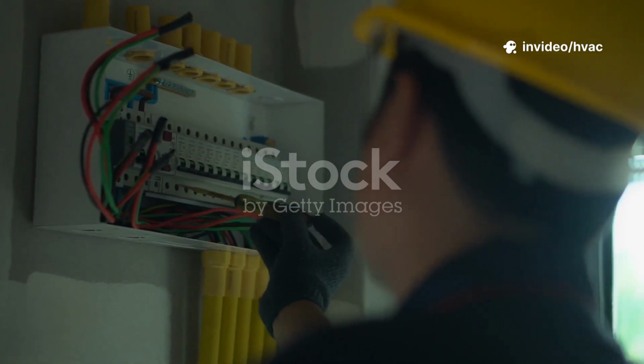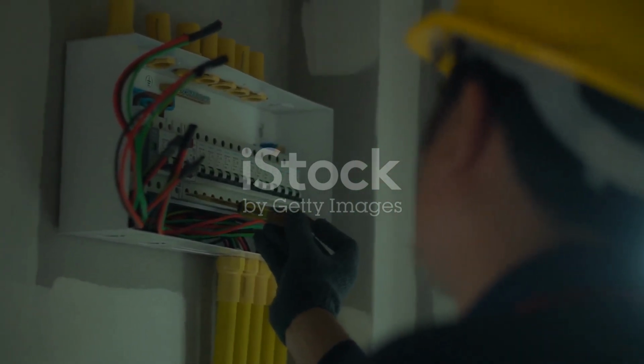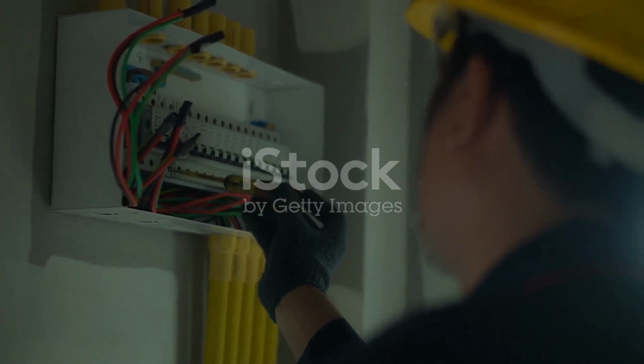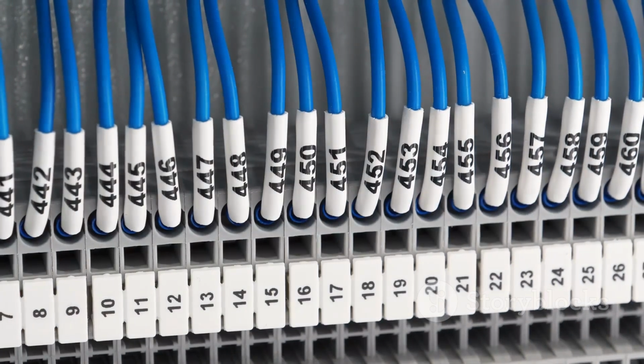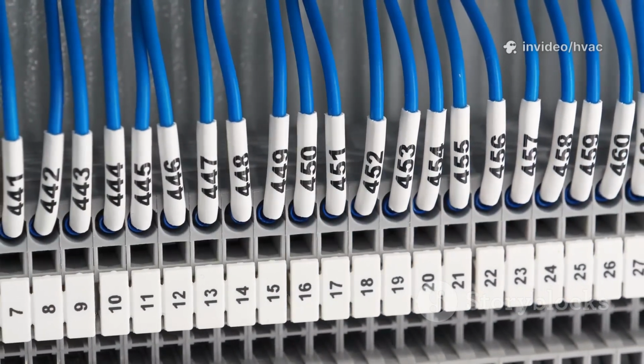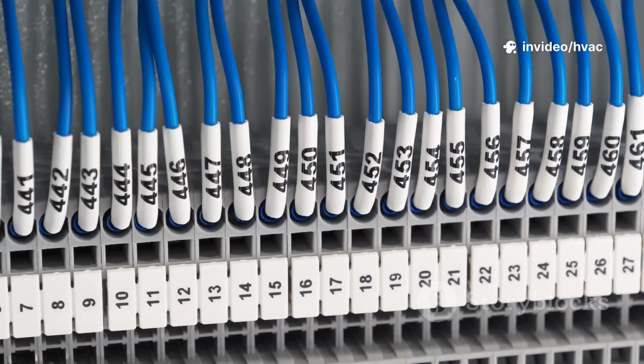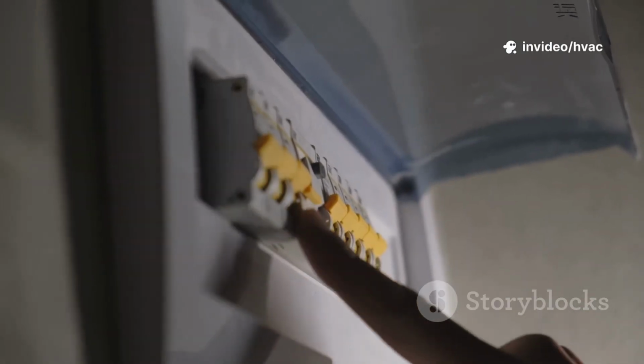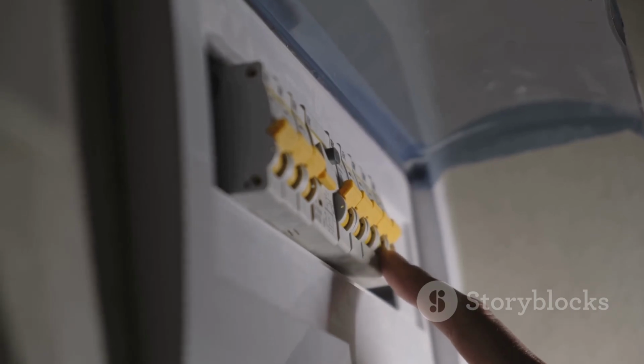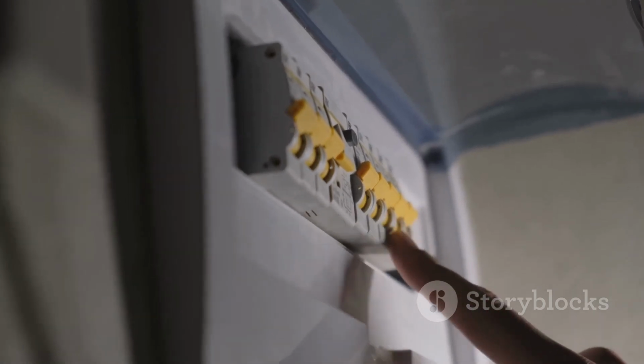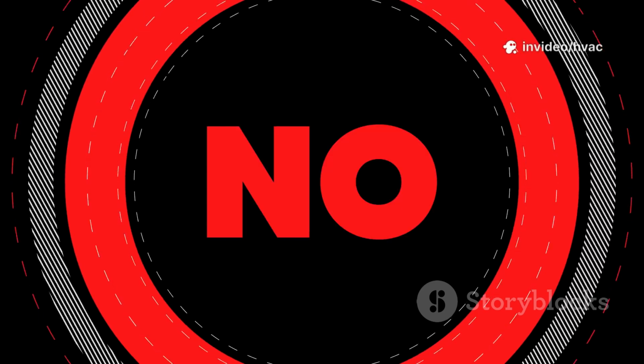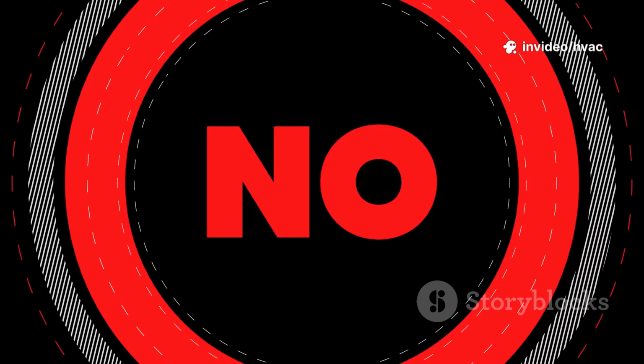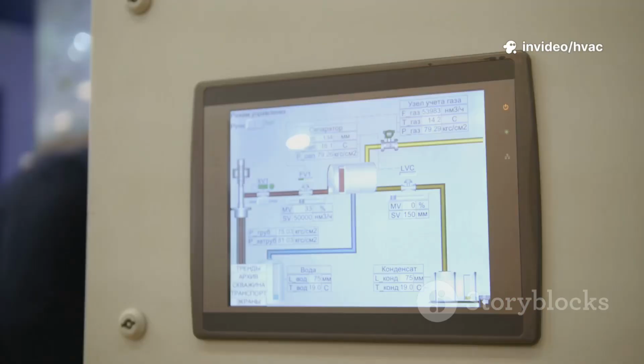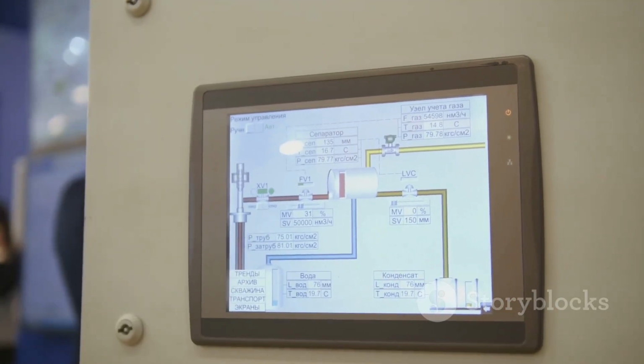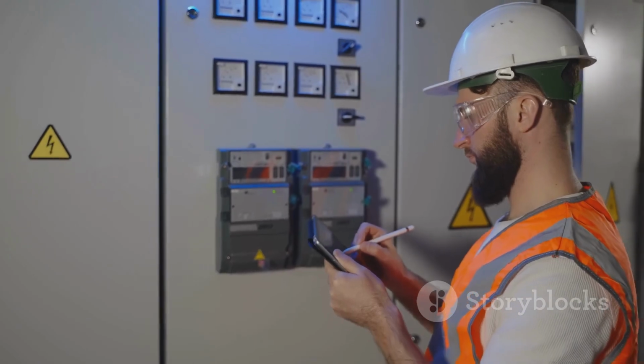At the heart of every interlock is a simple but crucial choice. Do you use a normally open, NO, or normally closed, NC contact? This decision shapes how your safety logic works, and it's vital for both safety and reliability. Here's the basic idea. A normally open, NO contact is like a door that stays open until you close it. No current flows until the device is activated. A normally closed, NC contact is like a door that stays shut. Current flows until you open it by activating the device. So how do you choose? Let's break it down step by step, using practical HVAC examples.